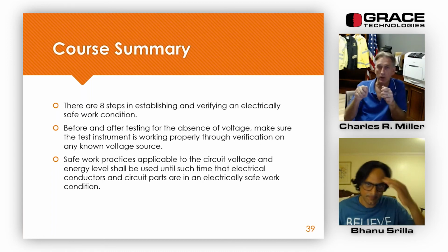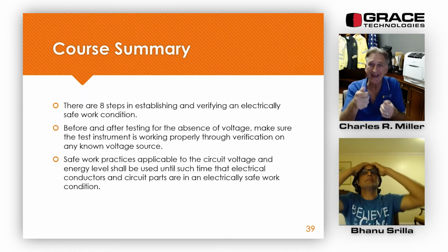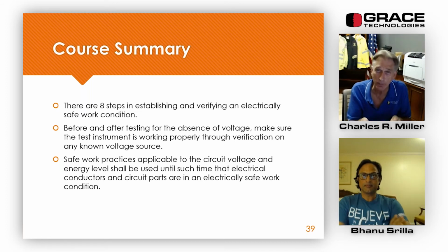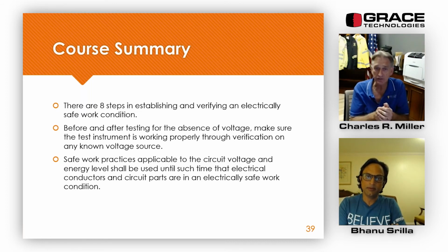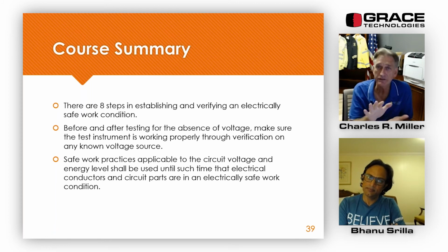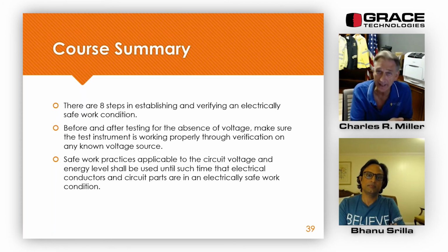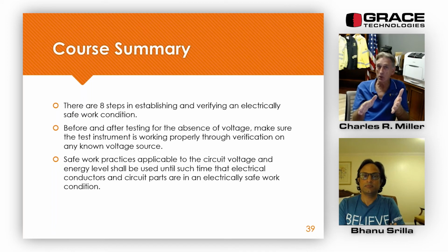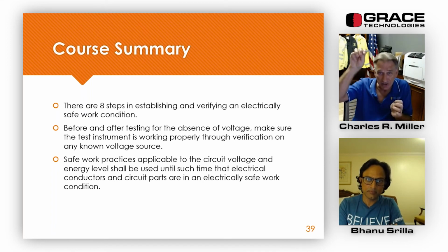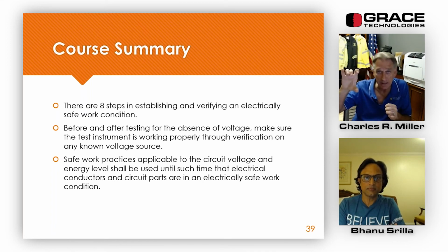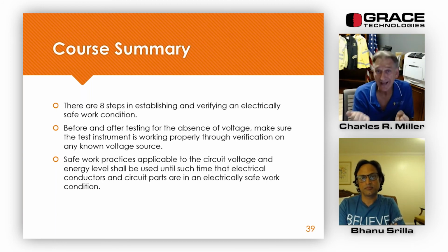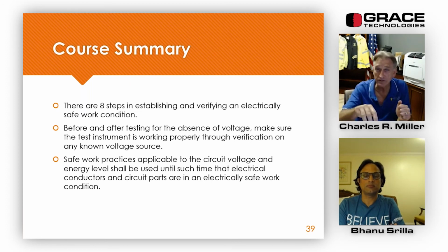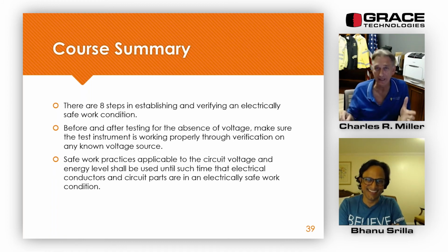That can be where, like Grace's, you can check from the outside of the cabinet without opening it up to verify the absence of voltage. There are absence of voltage testers, but with this new wording, that's just the very line side of that breaker coming in the very top that's been tested. To be able to open the cabinet up, you're going to have one of those devices on every component in that cabinet.